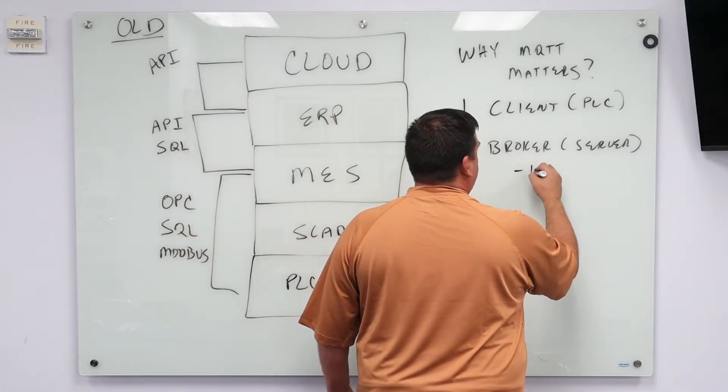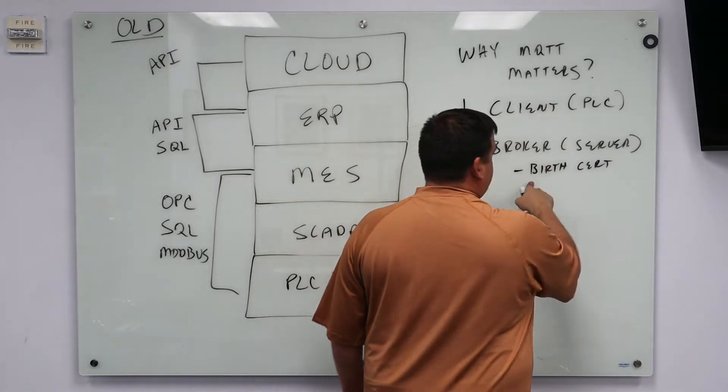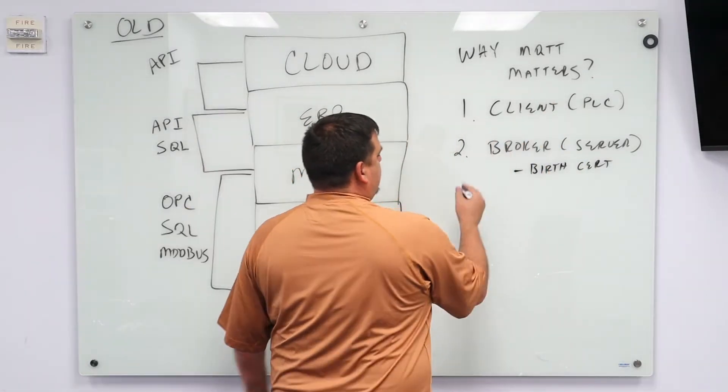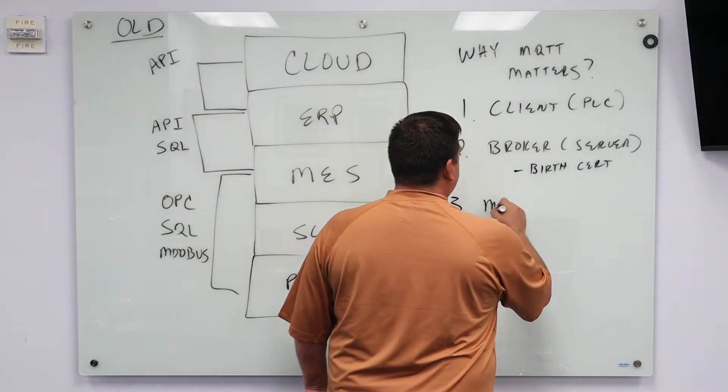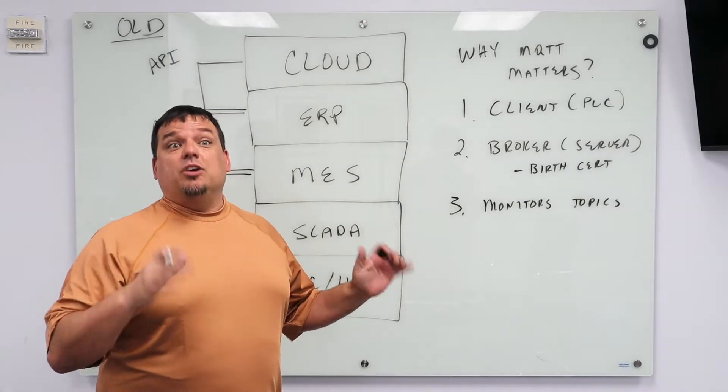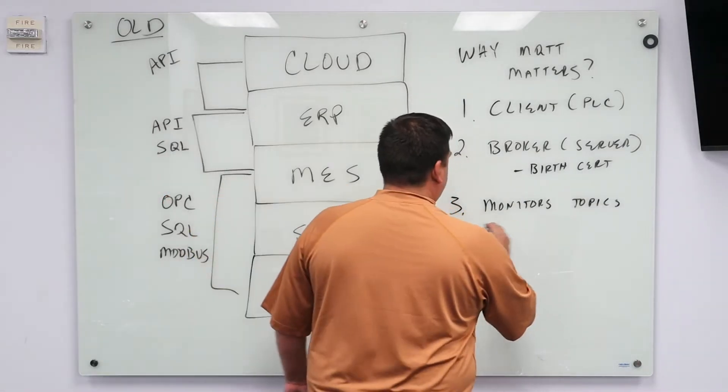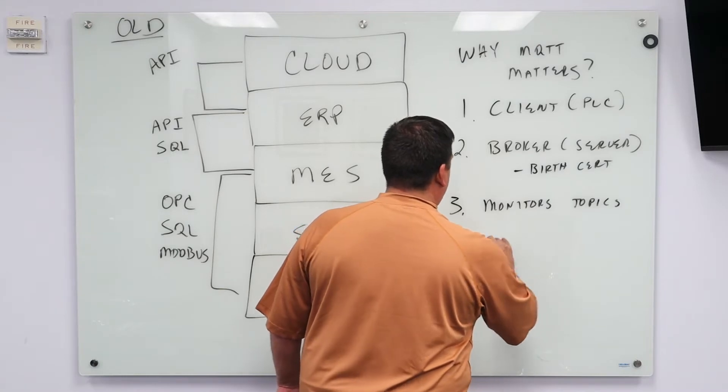The device sends a birth certificate. The client sends a birth certificate to the broker and the broker stores that information. And then the client monitors its topics, and we call in MQTT lingo is topic, but in industrial lingo it's tags.